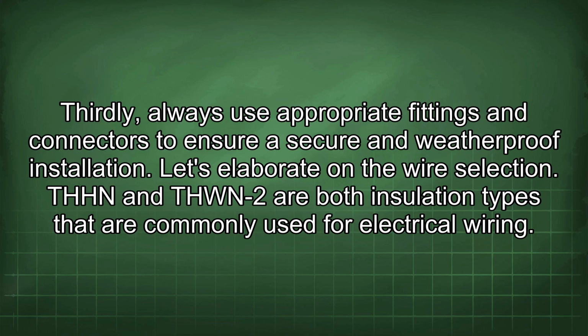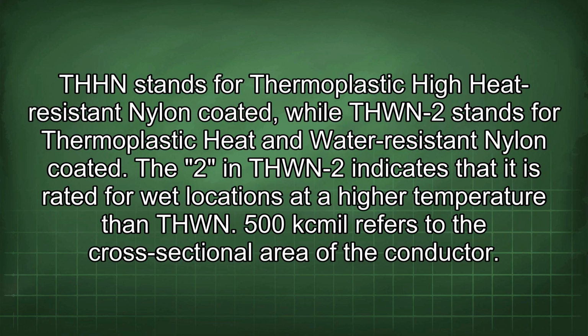Let's elaborate on the wire selection. THHN and THWN-2 are both insulation types that are commonly used for electrical wiring. THHN stands for thermoplastic high heat resistant nylon coated, while THWN-2 stands for thermoplastic heat and water resistant nylon coated. The 2 in THWN-2 indicates that it is rated for wet locations at a higher temperature than THWN.